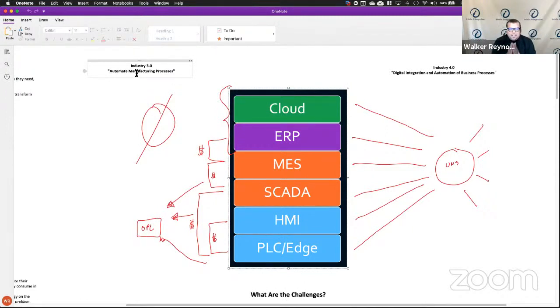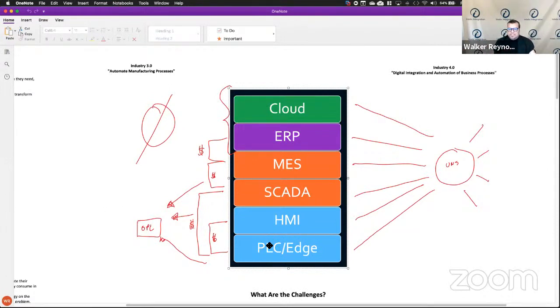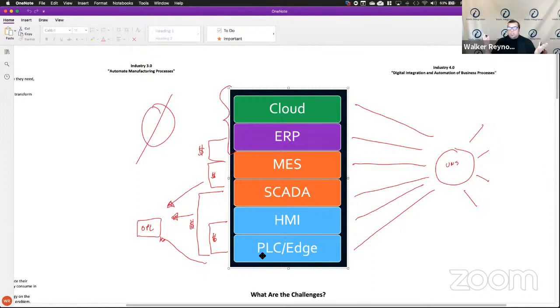I want to make a very important comparison. Doing it on the left-hand side — with linear integration — is like building a wall on top of a couch. Think of a PLC or a piece of edge software: when I build a machine using a ControlLogix PLC, am I going to have that PLC forever? No. Eventually that PLC is no longer supported — like PLC-5, SLC, they come to end of life. You need to remove them and put something else in place. Anyone who has done that knows it's incredibly difficult, expensive, and you lose production time. It becomes an even bigger pain if you have discrete linear connections between that PLC and your SCADA, MES, and ERP systems, because removing the PLC breaks those connections and you have to rebuild them from scratch.